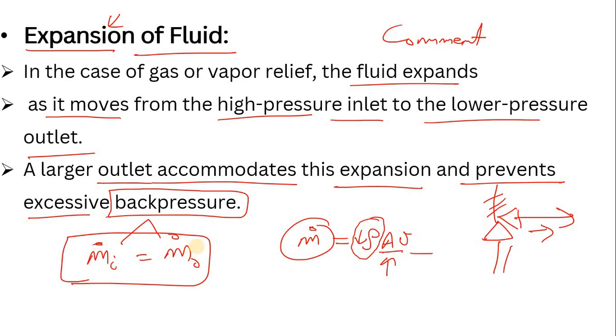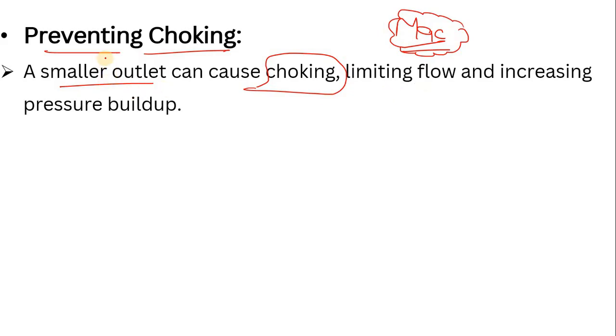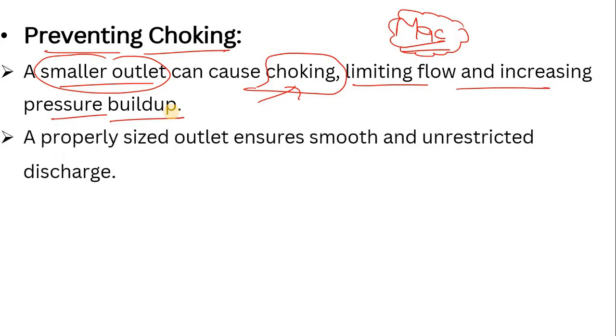The second most important reason is to prevent choking. If choking happens at the outlet when the PSV pops up, the fluid will not go to the destination and will come back. A smaller outlet can cause choking. That's why we calculate the Mach number in the case of gases or vapors. Can you let me know in the comments box: if the fluid is liquid, do we require the Mach number or not? A smaller outlet can choke the fluid, limit flow, and increase pressure build-up.